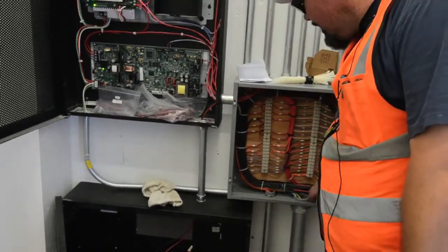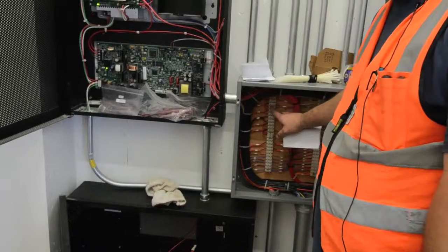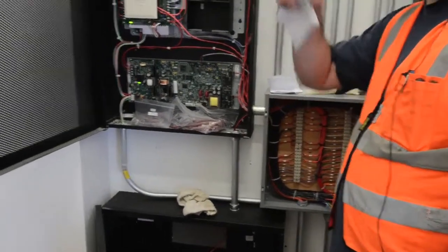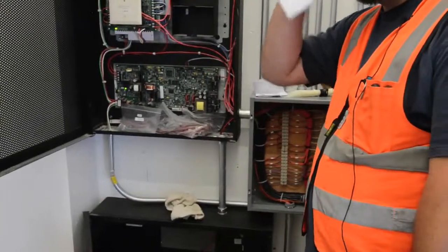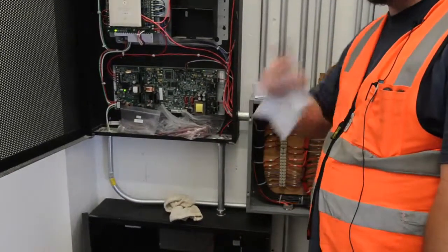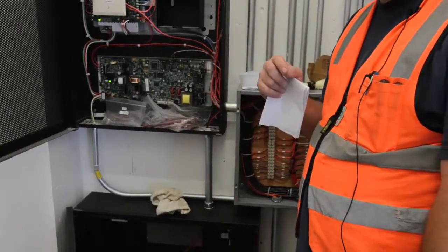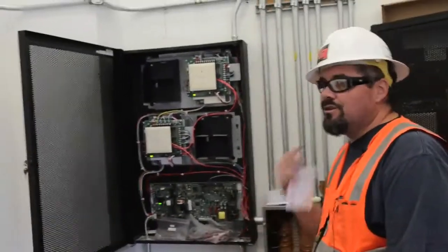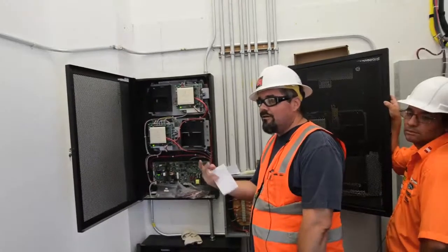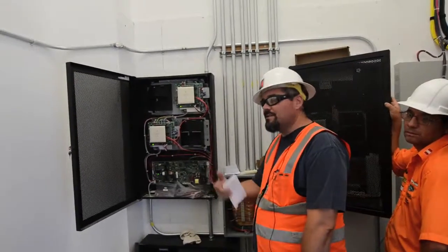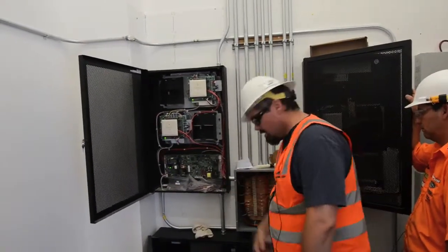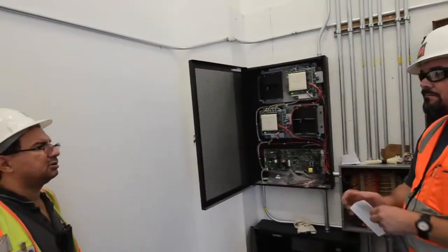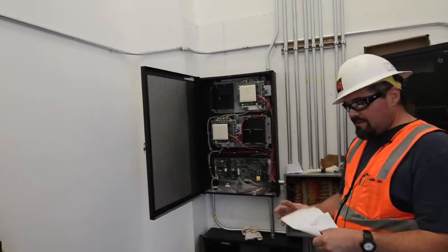And we have 2 loops. Loop 1 from the panel is going to be pretty much all your smoke detectors and water flow and tampers. The loop 2 is going to be all your modules for the CO2s. So it's sort of broken up also. So if you have a problem on loop 2, you'll know it's a CO2 issue or relay electrical issue versus like a regular smoke or a pull station. Which loop is the CO2 on? Loop 2.